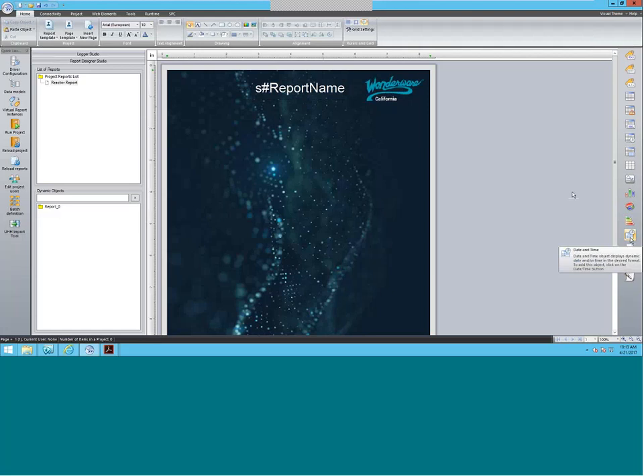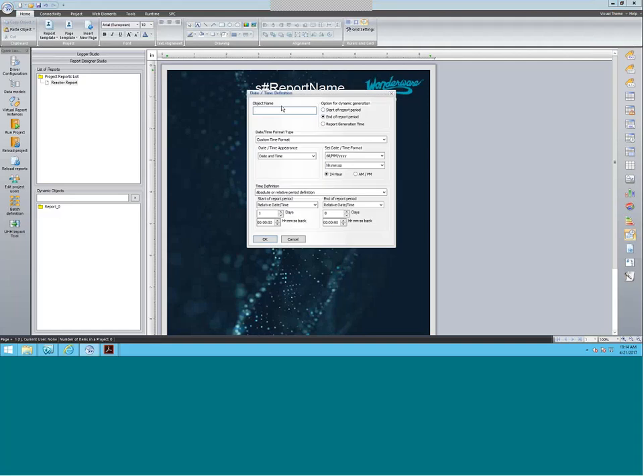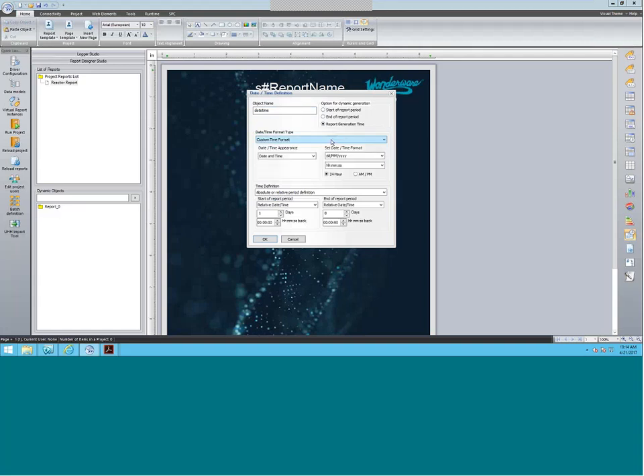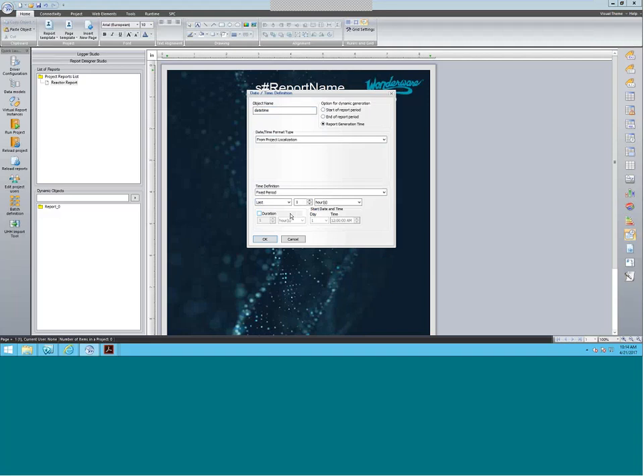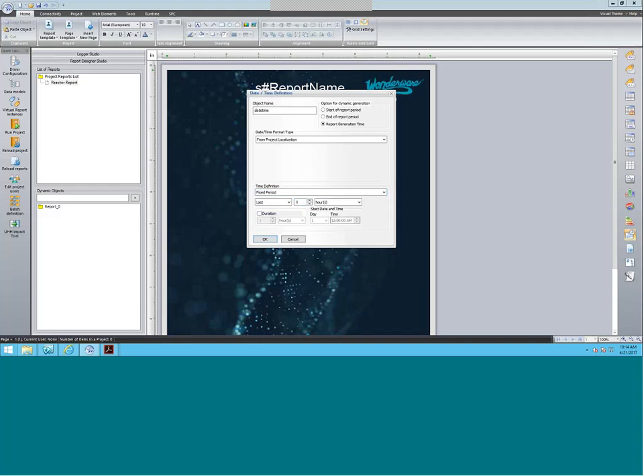The next thing I'm going to add is a date and time object. This date and time object allows you to put in a date and time showing when the report was generated. The objects usually come with an object name to help you define what the objects are. I'm going to do this one at the report generation time. There are a couple of different time formats you can set. The one I use the most is project localization — this gives me the timeframe that my computer is on, so it's easy to run my report without worrying about the time zone. Time definition allows you to do an absolute or relative period of time, as well as a fixed period of time such as last hour.